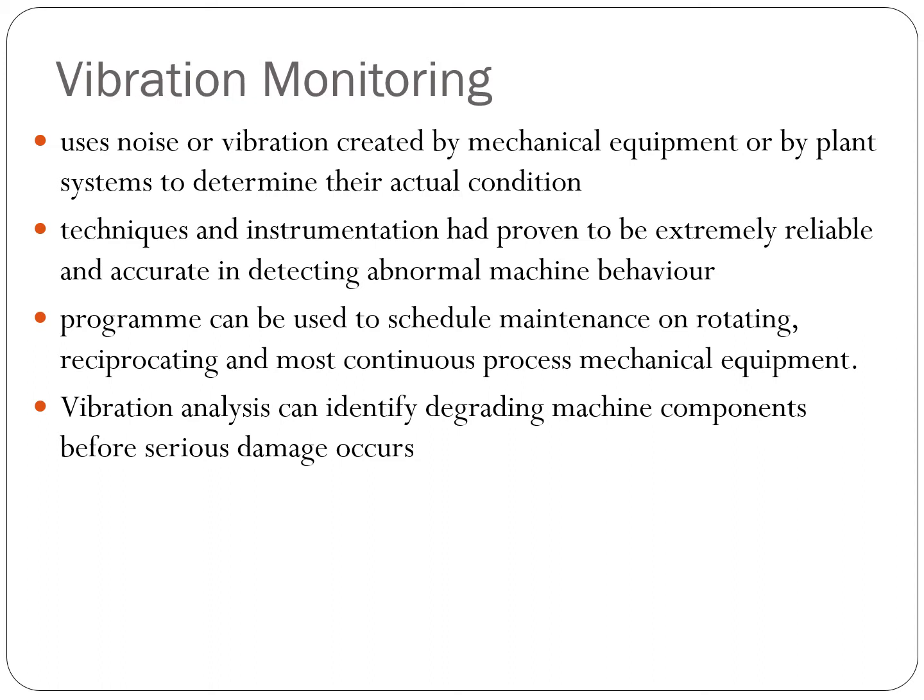The program can be used to schedule maintenance on rotating, reciprocating, and most of the continuous process mechanical equipments. Vibration analysis can identify degrading machine components before serious damage occurs. The measurements can be taken on the machine bearing casing with accelerometers.